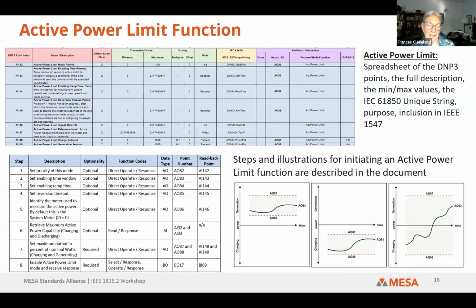Some of it is required, like setting the maximum output percentage and then enabling the function. On the bottom right are the responses: it could just limit generation, but there can also be a limit to generation along with a minimum requirement for some export — so the export can actually be bound by a sort of bandwidth of requirements.